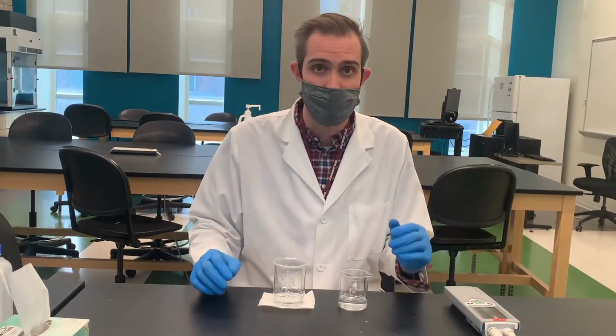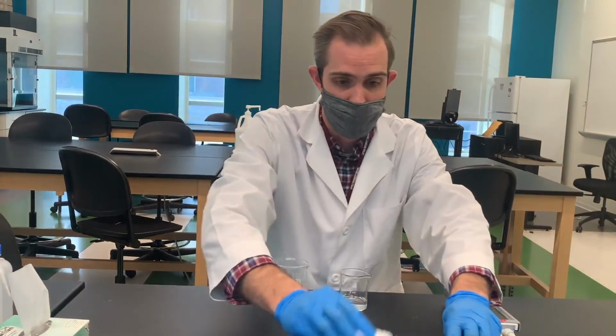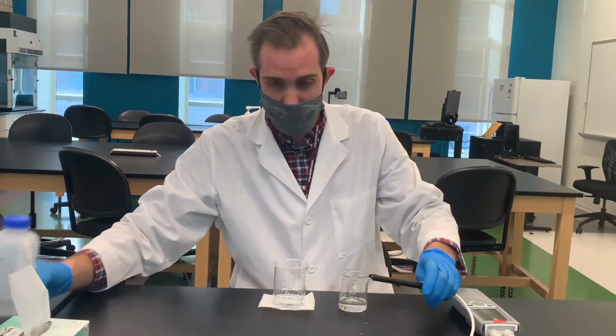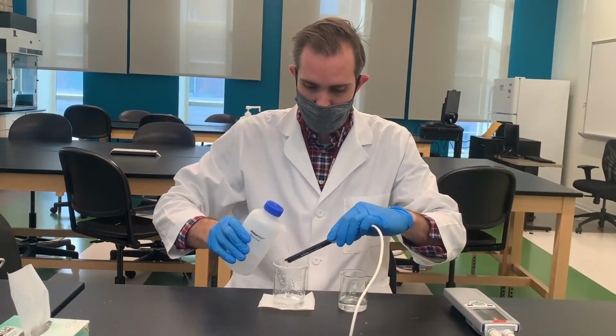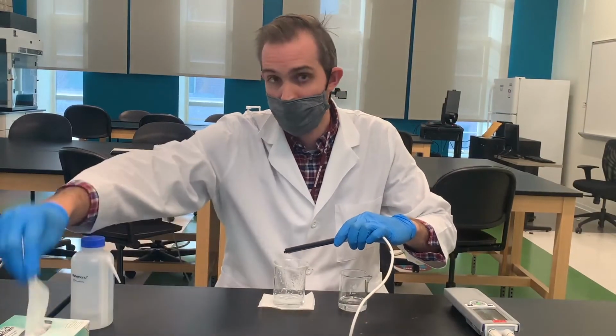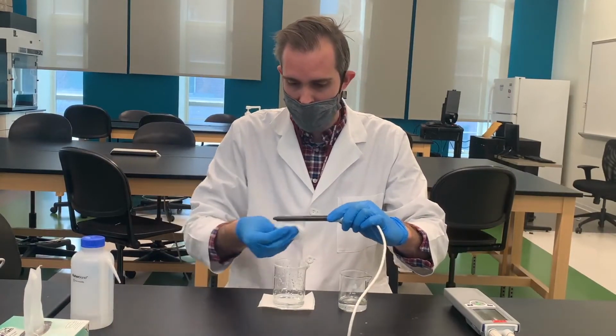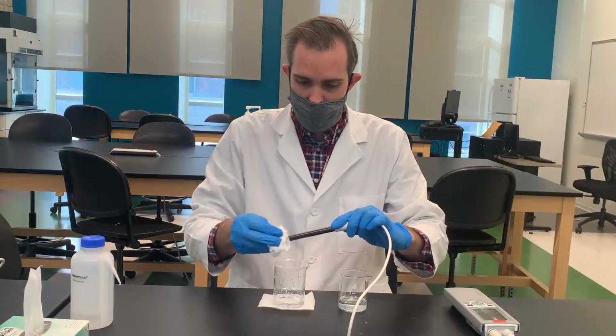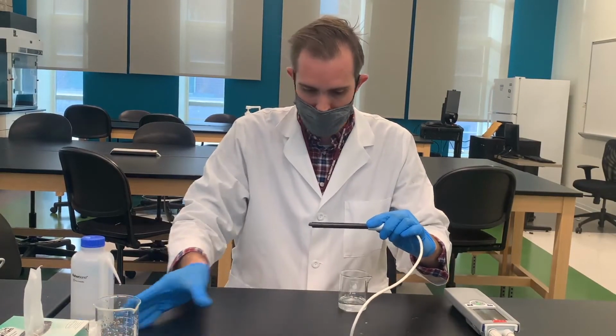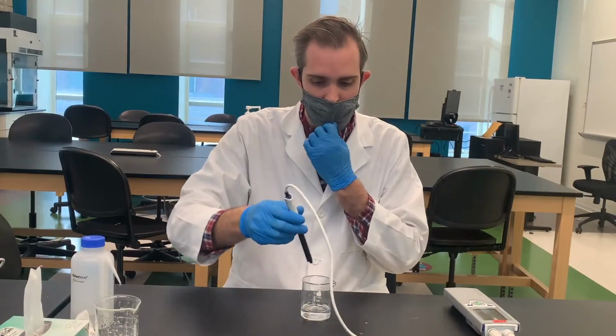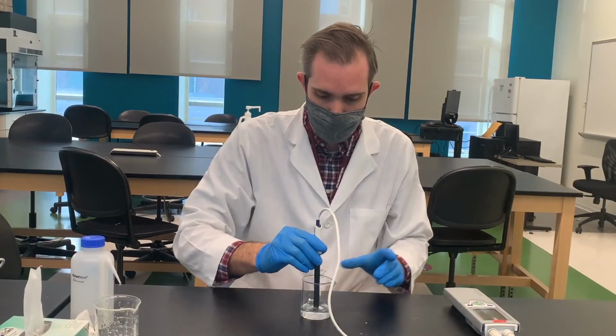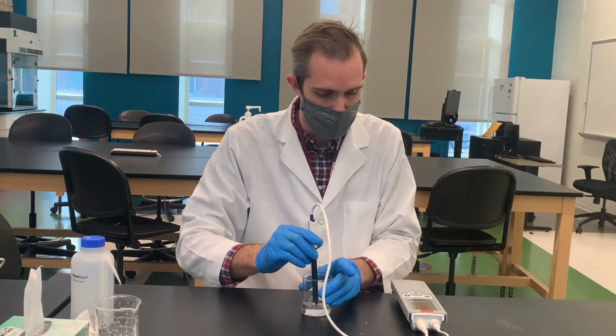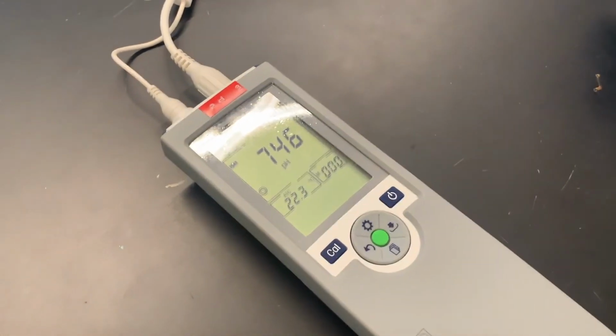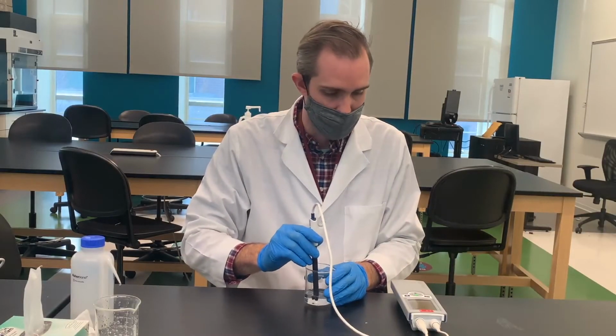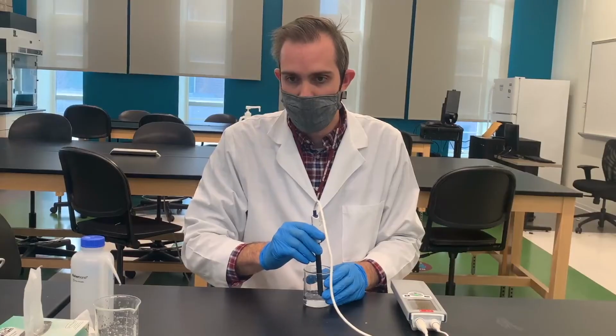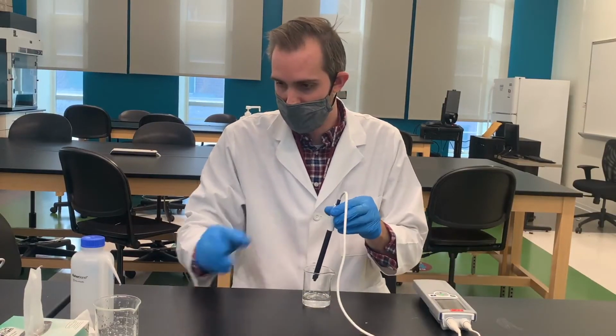All right, so now we're ready to actually take the measurement of the pH of an unknown substance. So we're going to go ahead and start by rinsing the probe with DI water and drying it off with a chem wipe. All right, and then you're going to take your solution that you want to measure the pH of, and you're going to insert the probe in and start to gently swirl it around with controlled swirls. And you're going to press the green middle button on the pH meter 1 time, and you're just again waiting for that A to stop. Once it has, go ahead and record the pH and the temperature.